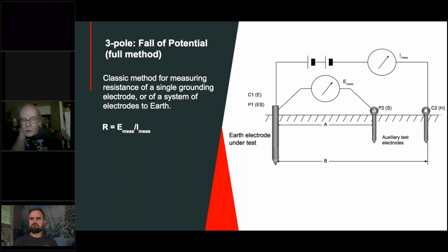Good high-end testers typically will now give you the ability to adjust your test frequency. 128 is just typical, but in many cases you'll have a tester that can adjust the frequency, and so you look for the quietest frequency to run your test.